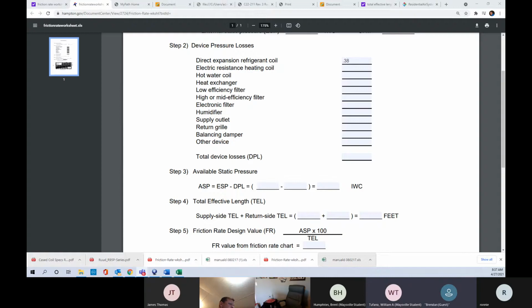If I'm reading the chart right, I think the 1-inch MERV 13 has an initial resistance at 1,000 CFM of around 0.2 for a 1-inch.